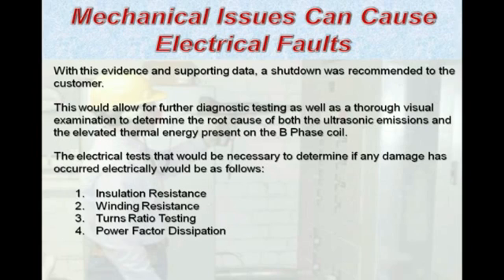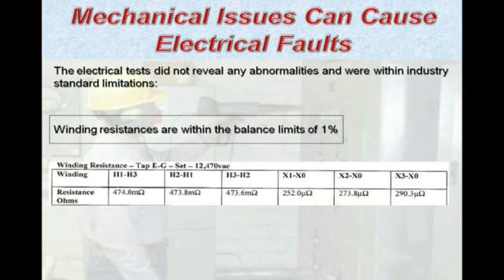The electrical tests that would be necessary to determine if any damages occurred are the typical ones one might use on this type of equipment. They would include insulation resistance on the winding insulation, the winding resistance measurements, the turns ratio values for the coils within the transformer, as well as power factor dissipation testing. In other words, tan delta, finding out how much watt loss is occurring through the winding insulation, which could be a measure of degradation. The electrical tests that were performed by a third-party company revealed no notable abnormalities, and most of them were within the industry standard limitations.